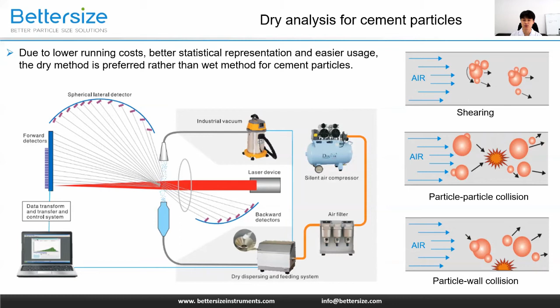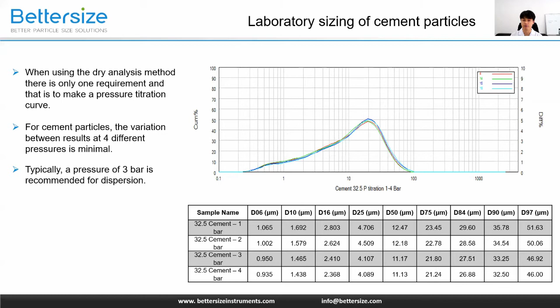This involves measuring the cement at 4 different pressures, typically from 1 to 4 bar. For many applications in other industries, results can change at different pressures, but as we can see in this figure, the variation between results at 4 different pressures is minimal. Typically, a pressure of 3 bar is recommended for dispersion in conjunction with a vacuum to suck away the dispersed particles after they have exited the measuring cell.